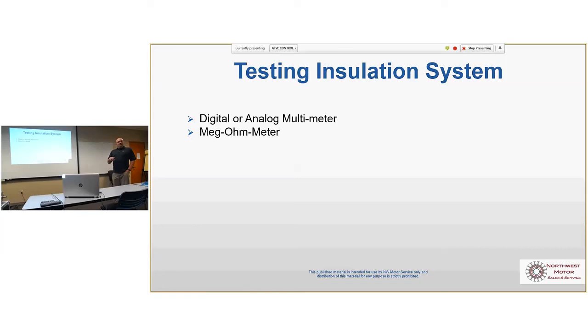So we're testing to see if a motor's grounded or not. Sometimes it's cold when you do it, so it doesn't give you the conditions. It's not testing turn-to-turn or phase-to-phase issues. To do that, you need to do a surge test, and it's nothing you can do with a Megger. So don't feel bad, but just know that all it's really doing is telling you if the motor's grounded or not. You can also see if you have a complete circuit. If you go from one phase to another, this should read really low. And with resistance on your multimeter, you could do phase-to-phase resistance to make sure you don't have an open circuit. But really, you're only going down to 1 decimal place on a handheld multimeter, and that's not accurate enough to tell you if there's a winding problem. You need something with a Kelvin bridge in it for more accuracy.